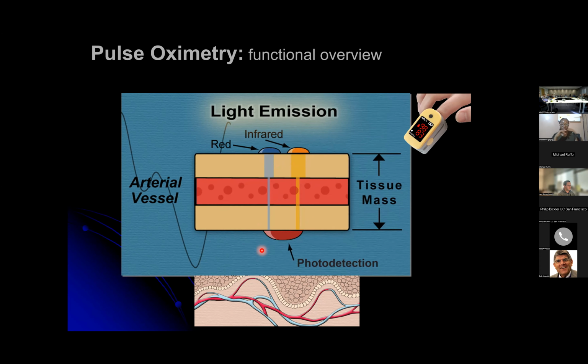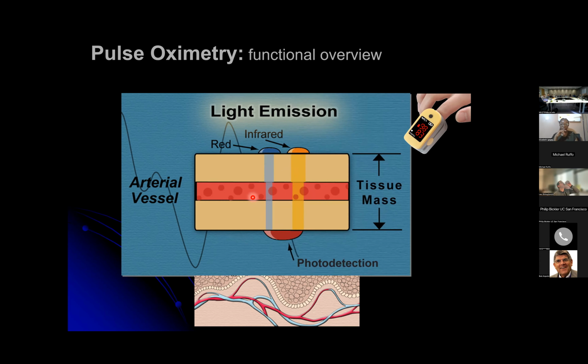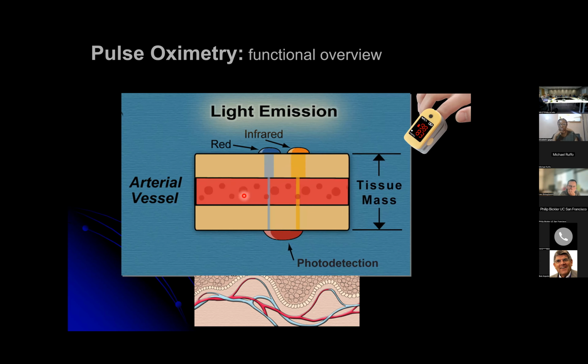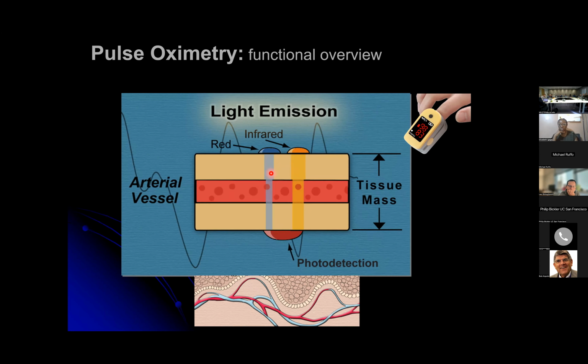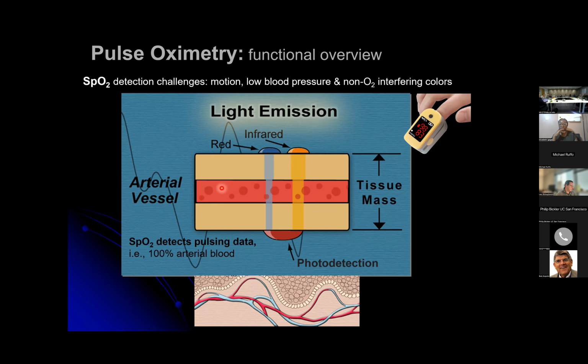That optical detector is challenged by the tissues that are in between. And the tissue of greatest interest are these circulating red blood cells that are picking up oxygen and delivering it to the tissues that need to metabolize that oxygen. And as you note, as this light is emitted in a constant way, at a constant power, that light is reduced or absorbed or attenuated because of the color of that blood. So that's what we're talking about, is where are the challenges to this technology?